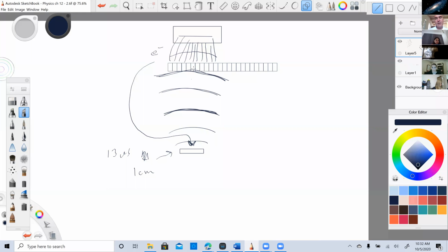It says to the middle transducer, which, I'm sorry, I keep saying transducer. The middle elements receive the echo first. The outside elements receive it just a little bit later. Up in the electronics, we say, no, we're going to dynamically focus this. We're going to say, no, all of these echoes should have come back at the same time. So that's the way we're going to show it on our screen. All right, that was a mouthful.